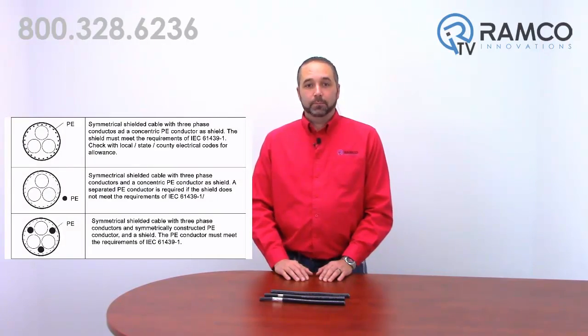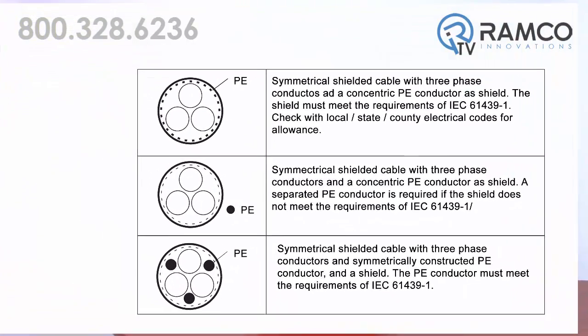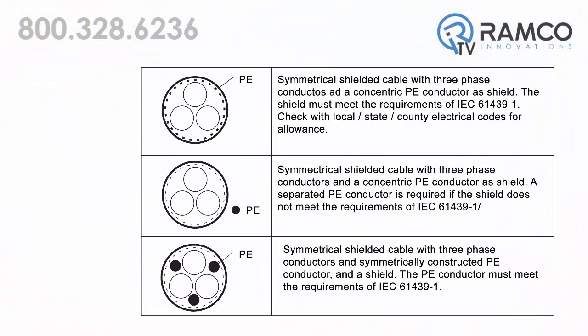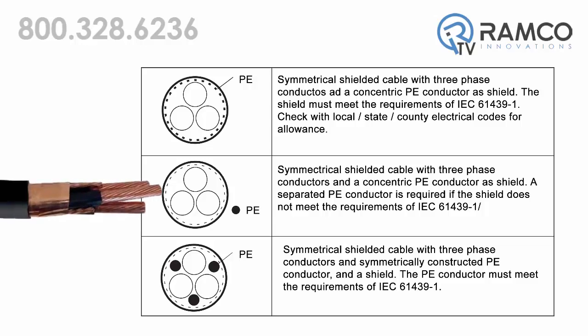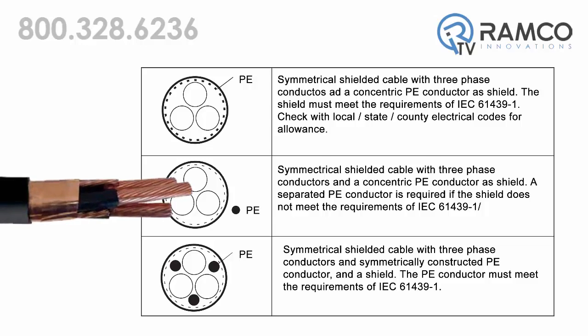One method to alleviate both of these problems is through proper cabling and connections. Many motor manufacturers, including ABB, recommend using cables that have a symmetrical arrangement of three-phase leads and three earth conductors covered by a concentric shield on large motors.